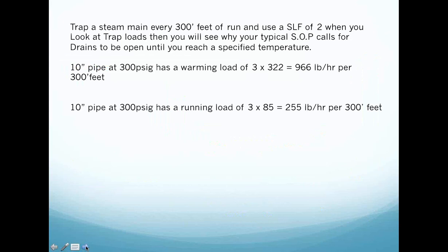So, a steam trap for a steam main every 300 feet of run, and use an SLF, safety load factor, of 2.